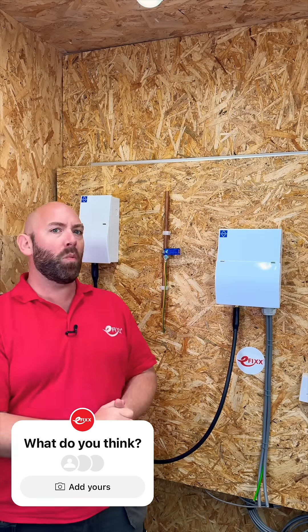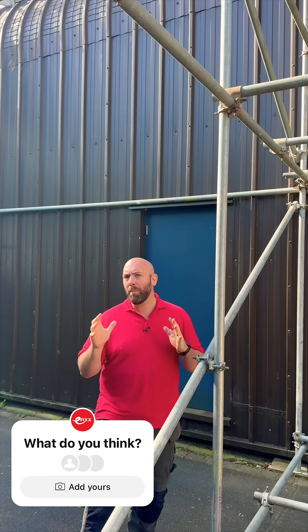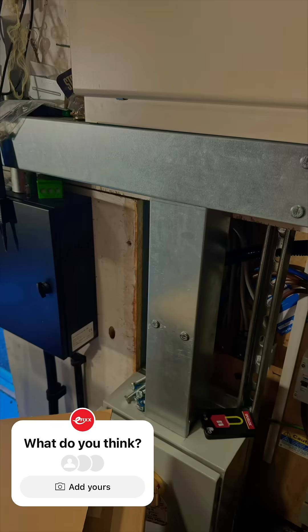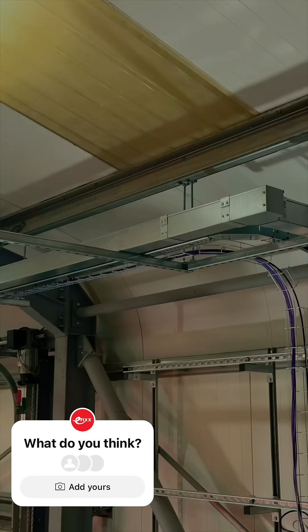Okay then, Quizzy Bob, let's have a look at what a parallel path actually is. A parallel path is something which is metal and offers a return path back to earth — something like tray, basket, trunking, an RSJ, or any other extraneous metal parts which could offer a lower resistance in certain of the tests.